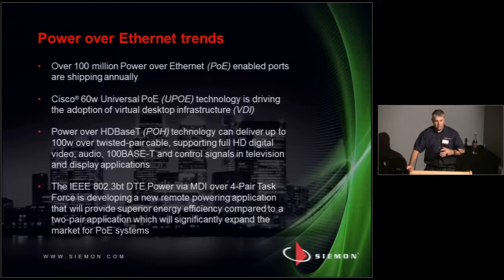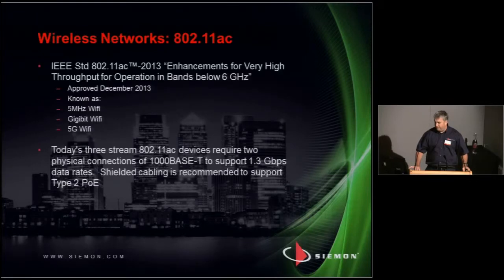With those cables not in an air-conditioned space, and we all like to see our cables neat and tidy, we're going to bundle them together. And we have found through research that the cables are getting really warm. PoE plus alone increased the cable temperature by 10 degrees C. And this is another one.